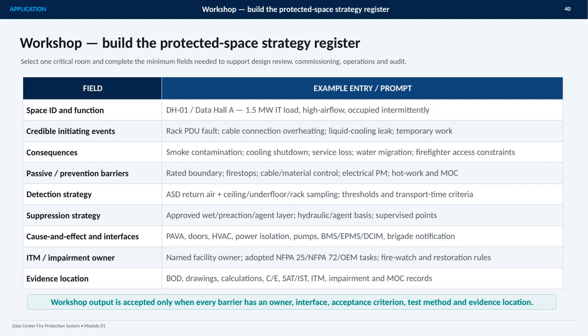This workshop turns the protection concept into a usable strategy register for one critical room. Select a space, such as Data Hall A, and document enough information to support design review, commissioning, operations, and audit. Start with the space function, credible initiating events, and consequences. For example, consider rack PDU faults, overheating connections, liquid cooling leaks, or temporary work. Then connect those events to smoke contamination, cooling shutdown, service loss, water migration, and access constraints.